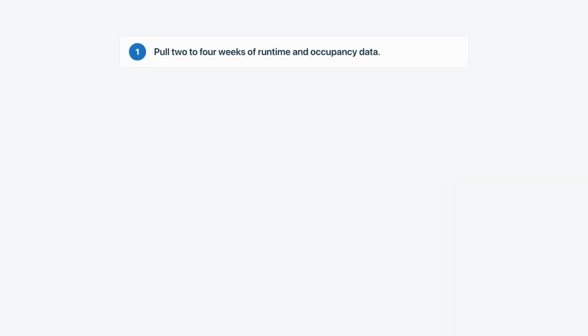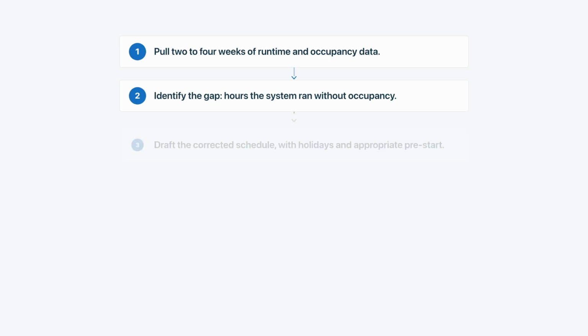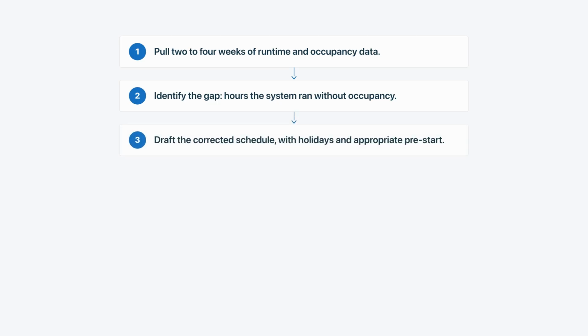The correction process is 5 steps. Step 1 is pull 2 to 4 weeks of runtime and occupancy data. For a simple schedule, 2 weeks of data may be enough. 4 is probably better if the building has a lot of variability across days of the week. Step 2, identify the gap. Look at the runtime curve and the occupancy curve, and the area between them is the waste. Step 3 is to draft the corrected schedule, and this includes the occupancy hours, the correct pre-start window, holidays for the coming year, and any special use exceptions.